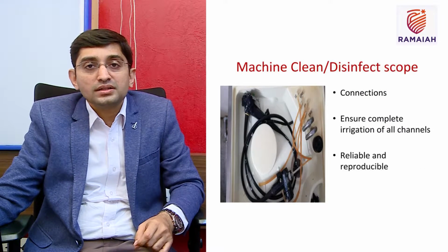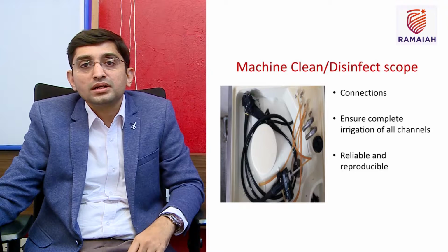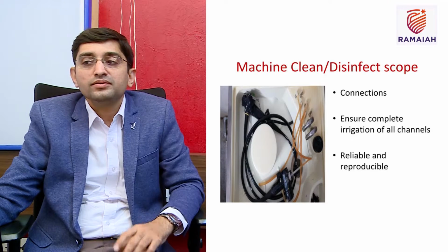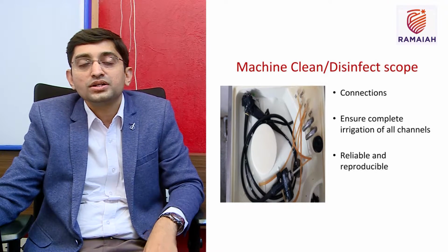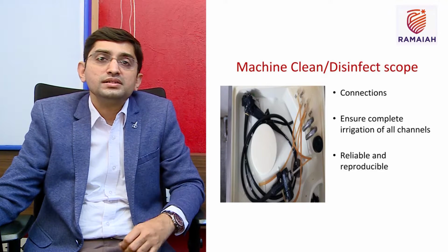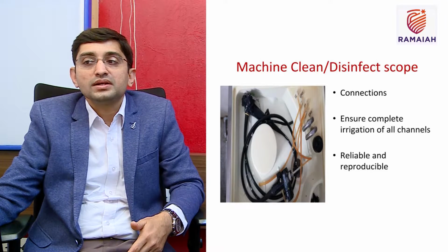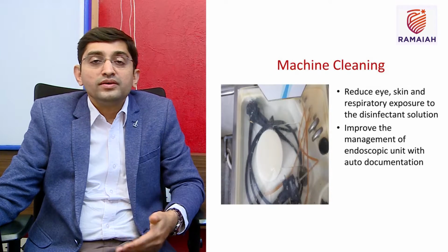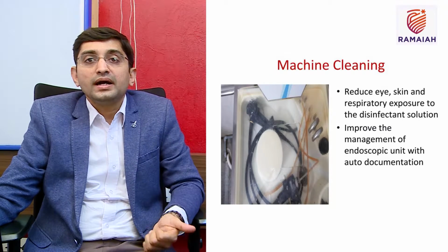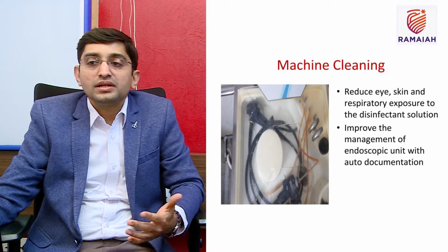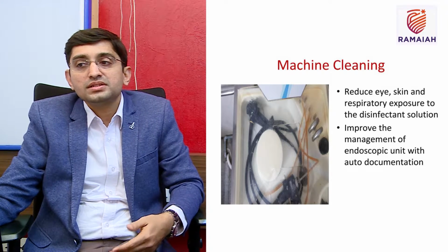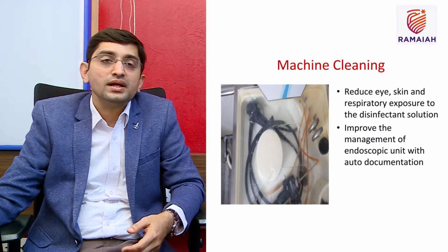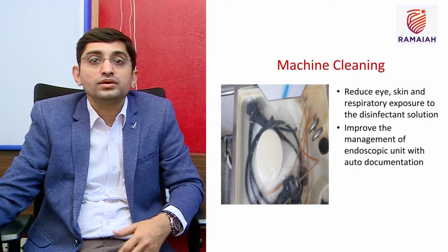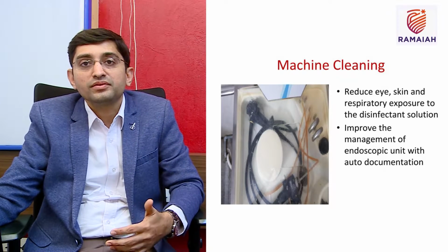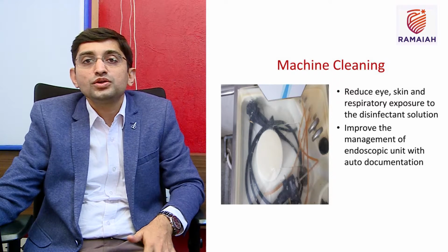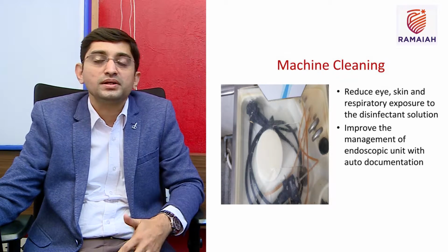Before we start the endo washer, we should ensure that all the connections are correctly connected. We should ensure that complete irrigation of all the channels is done. The advantage is that because it is a machine, it is reliable as well as reproducible. Whenever we use open glutaraldehyde, there will be eye, skin as well as nasal irritation. In a machine scenario, it always reduces the exposure of eye, skin and respiratory system, and it will improve the endoscopic unit function by disinfection. We can always keep a record of each scope, of how many cycles of disinfection have been done.